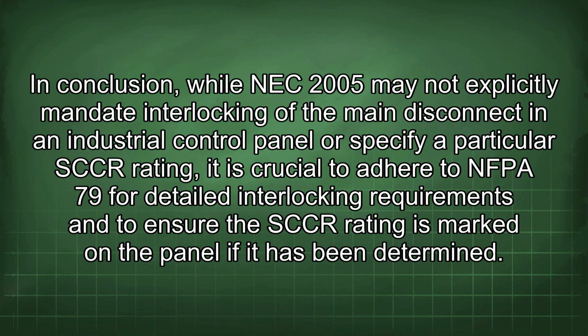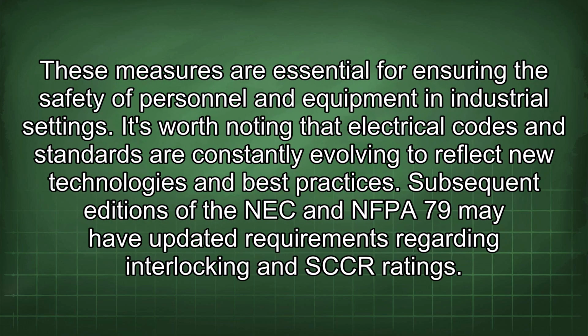In conclusion, while NEC 2005 may not explicitly mandate interlocking of the main disconnect in an industrial control panel or specify a particular SCCR rating, it is crucial to adhere to NFPA 79 for detailed interlocking requirements and to ensure the SCCR rating is marked on the panel if it has been determined. These measures are essential for ensuring the safety of personnel and equipment in industrial settings.